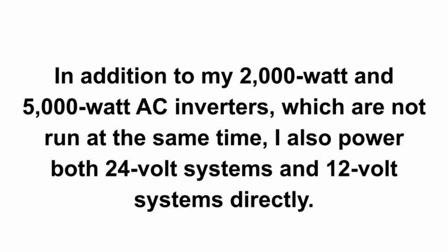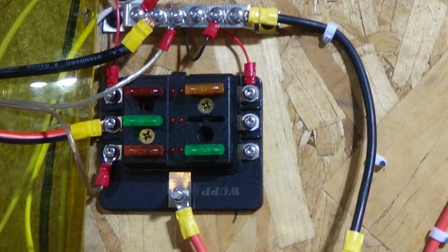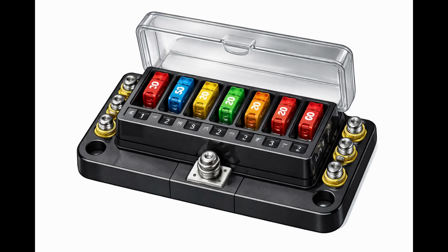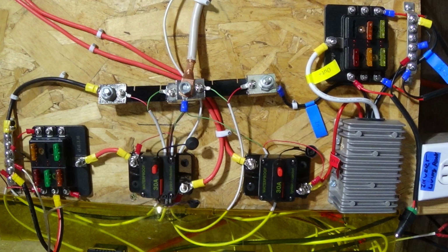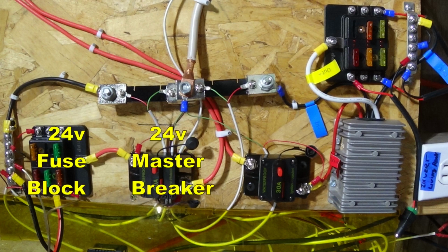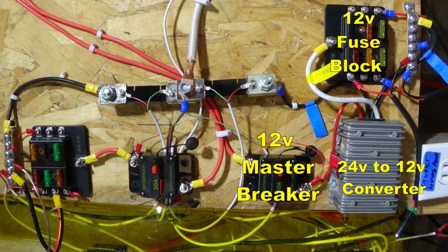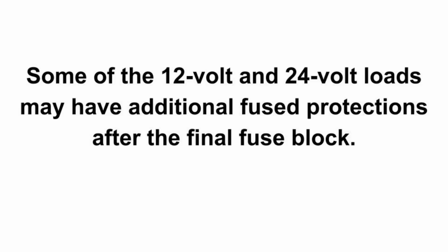In addition to my 2000 watt and 5000 watt AC inverters, which are not run at the same time, I also power both 24 volt systems and 12 volt systems directly. All 24 volt loads are protected by fuse blocks near the battery and by fuse blocks at the point of use. Additionally, the 12 volt loads have another fuse block protecting them at the point of use. This gives me at least 2 layers of protection for the 24 volt loads and a minimum of 3 layers for the 12 volt loads. Some of the 12 volt and 24 volt loads may have additional fused protections after the final fuse block.